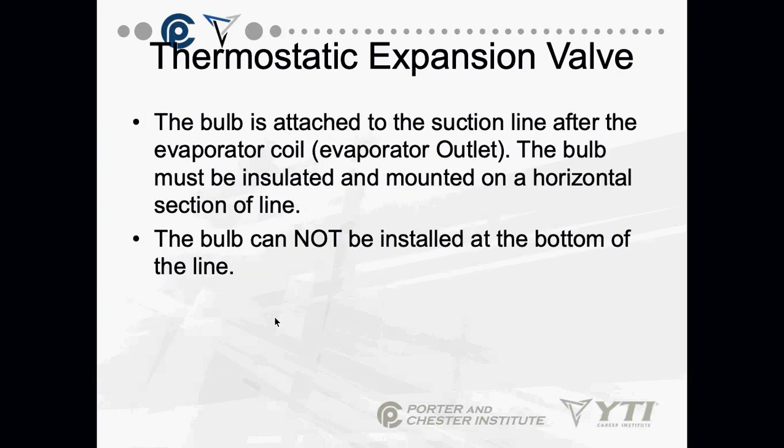The TXV has a little bulb. You have 2 ports on a TXV, or sometimes 3, which I'll show you. There's a temperature sensing bulb that's attached to the suction line after the evaporator coil. It's the evaporator outlet.